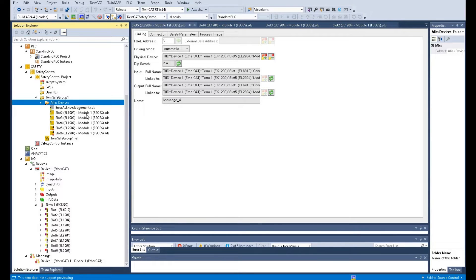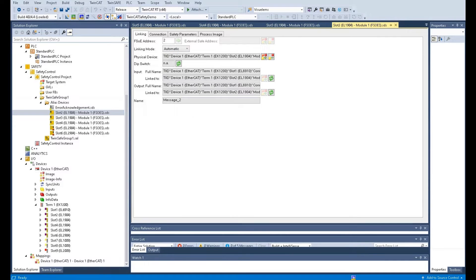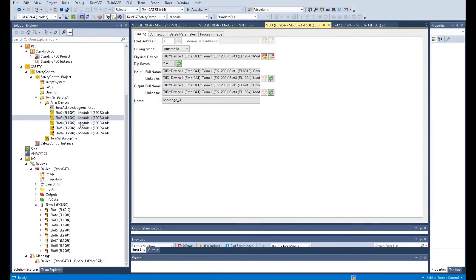If we go to the input safety devices — for example slot 2, EL1904 — and double click this area, we first need to double check the safety address. Personally I will set this address the same as the slot number. For example, this safety input is on slot 2, 3, 4, 5, 6, so the safety address is the same as the slot number. This safety address number must be the same as the DIP switch setting on the side of the safety card.